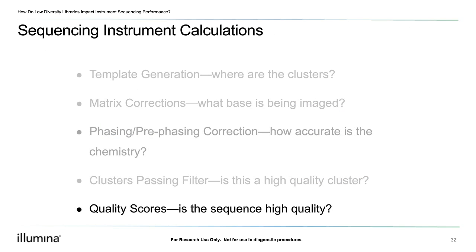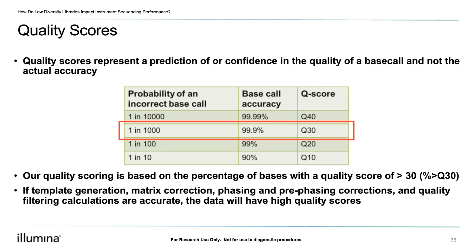We define quality scores as the probability of an error in the base call — not a measure of absolute accuracy, but an estimate of instrument confidence. A base call with a quality score of 30 has a probability of 1 in 1,000 of making an incorrect base call, so the higher the quality score, the higher the confidence and accuracy. If template generation, matrix correction, phasing and pre-phasing estimates, and quality filtering calculations are accurate, this will yield a high-quality base score. For low diversity libraries, each metric used for the Q-score calculation can be impacted, leading to a lower overall Q-score.